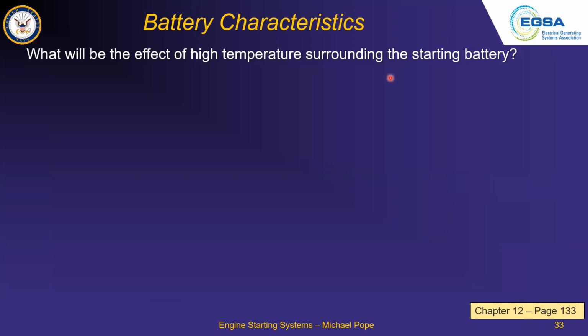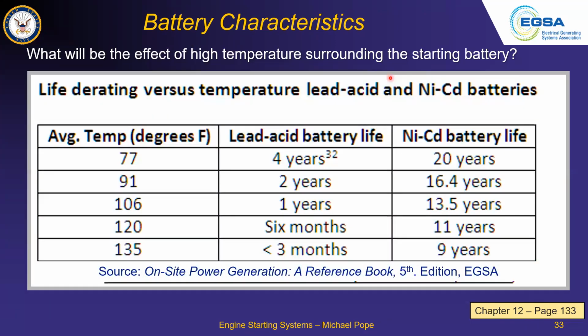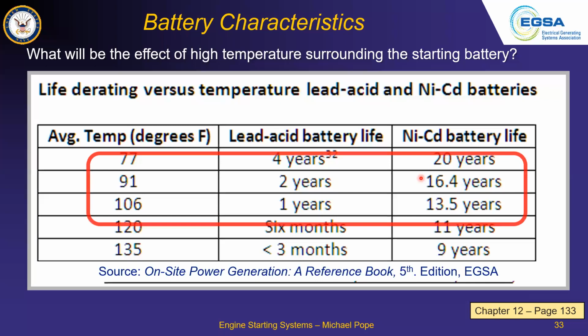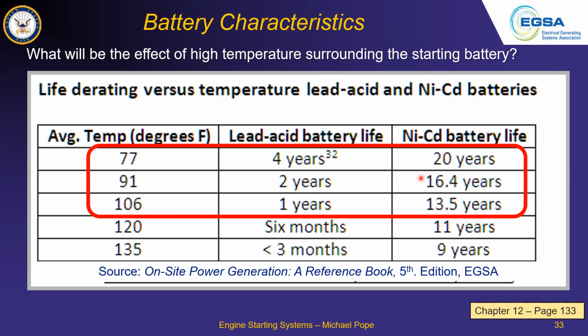So what is the effect of high temperatures for a starting battery? Kind of interesting. At 77 degrees in this study, you get about 4 years of life out of a lead acid battery. A NiCad, because of its technology, gets 20 years, no question about it. Increase the temperature to 91 degrees, and that reduces the life of the lead acid battery by half. The NiCad drops only a little, from 20 to 16 and a half years. At 106 degrees constant temperature, you can see what happens - actual mileage may vary.